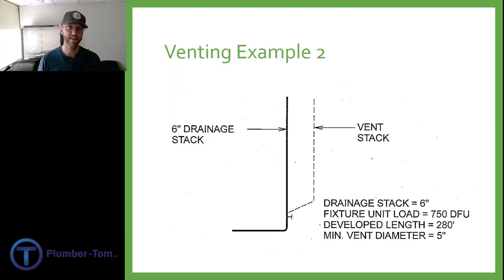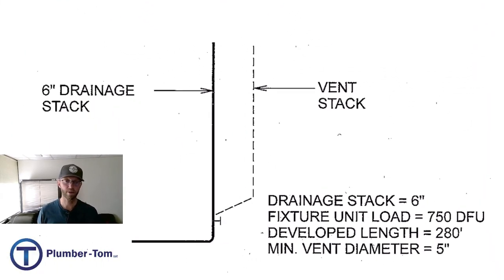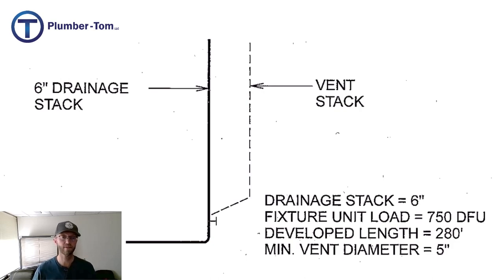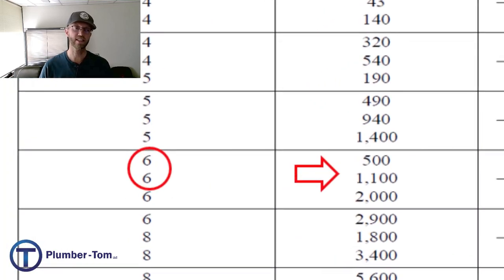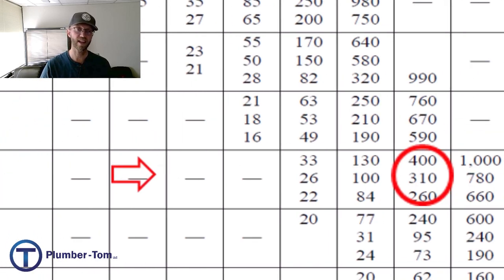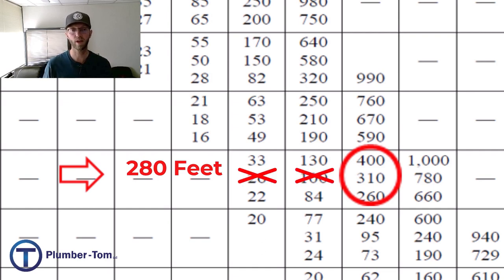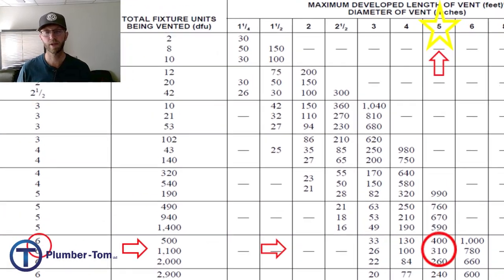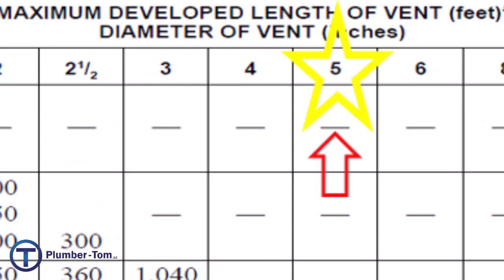Example two: we're dealing with a vent stack. The drainage stack is six inch, the total fixture unit load is 750 drainage fixture units, and the developed length is 280 feet. Going to the table, we find the six inch rows. 750 DFUs is more than 500 but less than 1100, so we settle in that row. Our developed length of 280 feet is more than 26, more than 100, but less than 310 — so we take that column and head straight up to the top. We find that we have a five inch vent pipe for that vent stack.